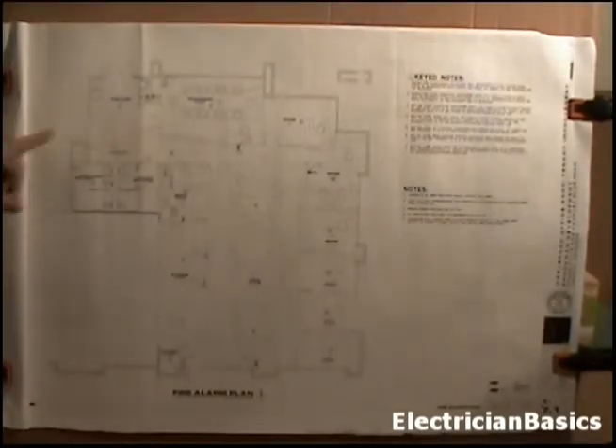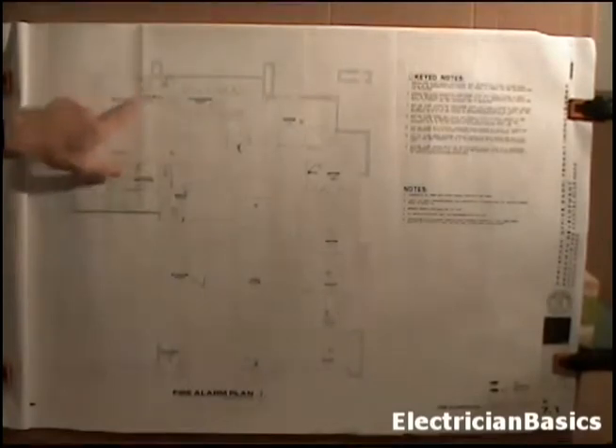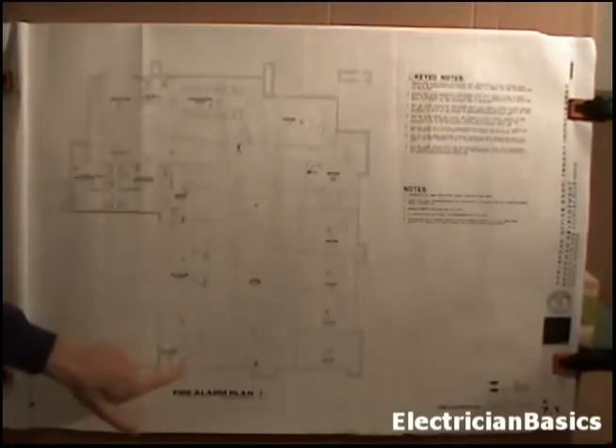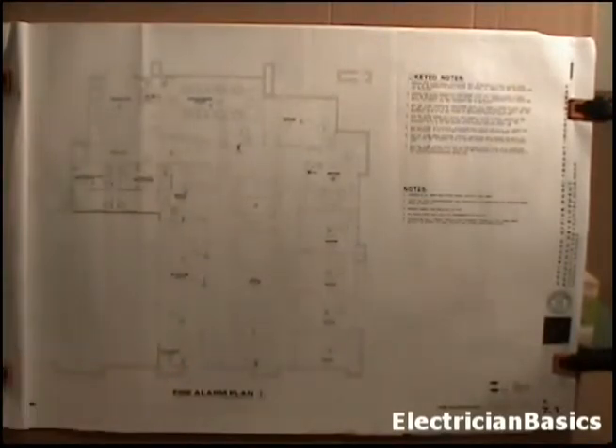Let's look at our key note 1 up here. We have it, and also down here by this door. And it points to a square with a P in it. Now that's your pull station, and that symbol's not listed in E0.1, but it says existing fire alarm manual pull station shall be relocated to new location shown, total of 2. Contractor shall provide and install all conduit and wire necessary for the relocation.